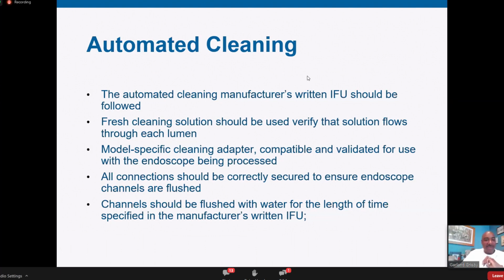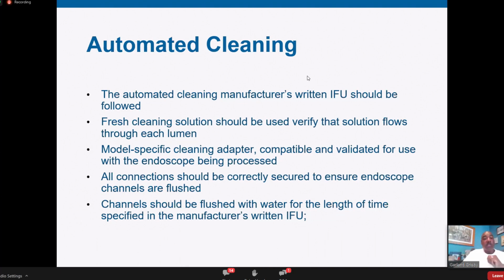It's not okay to modify the connectors. You want to make sure that you use the connectors that are meant for that particular scope that you're processing. All connections should be correctly secured to the endoscope, so you want to make sure that nothing pops off during the flushing cycle or the purging cycle. Channels should be flushed with water for the length of time specified by the manufacturer's written IFU.